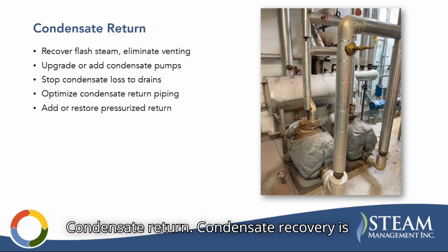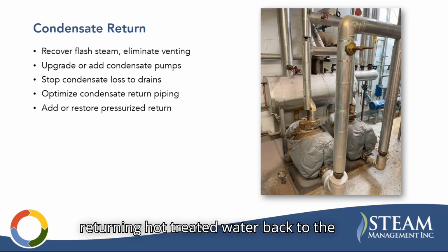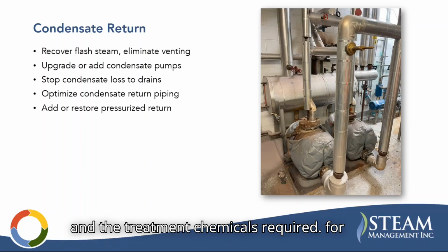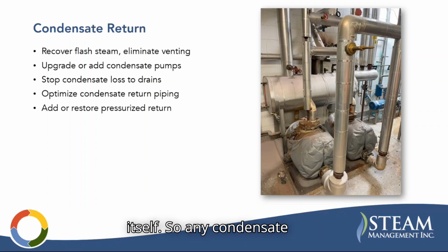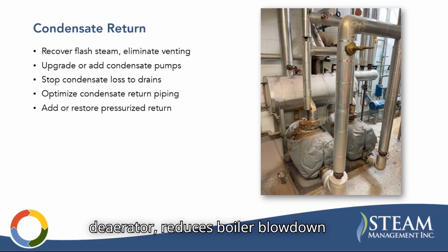Condensate return. Condensate recovery is critical because basically you're returning hot treated water back to the boiler house. So every bit of condensate recovered represents less cold makeup water needed for the system, and the associated heat required for that makeup, and the treatment chemicals required for that makeup, as well as the water cost itself. So any condensate return mitigates all of those losses and also reduces the deaeration load on the deaerator, reduces boiler blowdown because now you have less dissolved solids being introduced to your system through the makeup water. So it is critical to return as much condensate as possible.